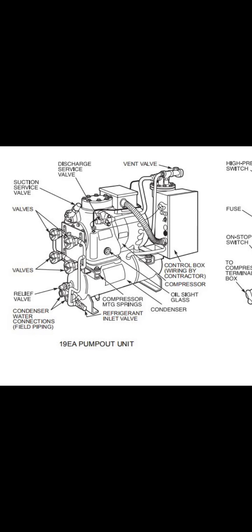The storage tank may not have a sight glass, I don't see one, but it has an electronic liquid level control switch. The level control switch will monitor that a safe level of liquid is coming. If liquid touches the switch, it will shut down the pump out unit. So this protection is there that you cannot see, but you cannot fool. This level switch will cut off the unit. The same way you transfer large vapor, until the pressure is down to zero. You stop the pump out unit and remove this line.